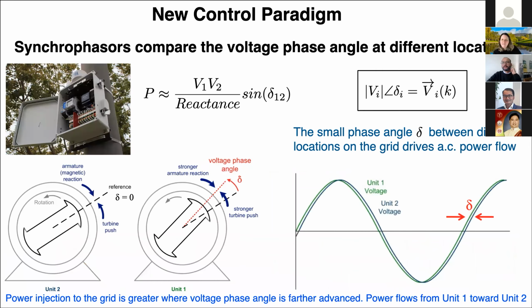To motivate this new control approach, which we termed phasor-based control, let's first define a synchrophasor. A synchrophasor is a time-synchronized measurement of the voltage magnitude and phase angle at different locations in the grid. In the transmission grid, the phase angle difference between two voltage waveforms as measured at two synchronous generators is what drives power flow, according to the equation in the slides.